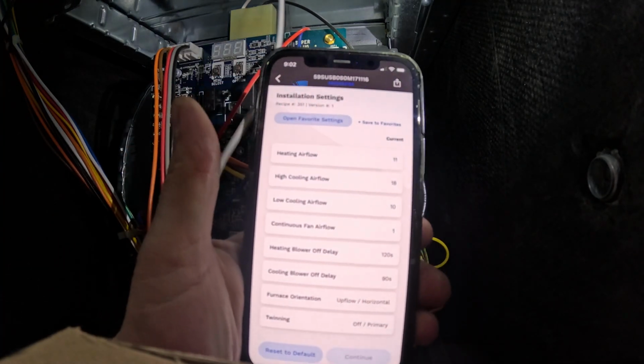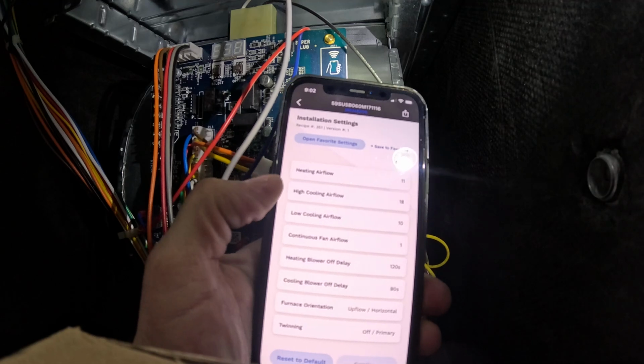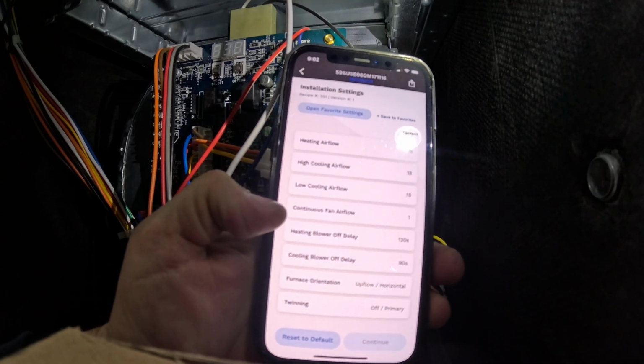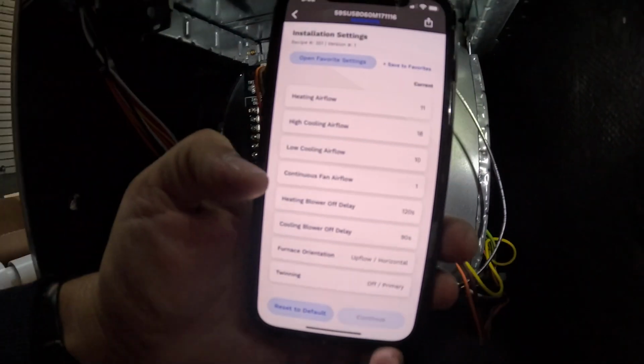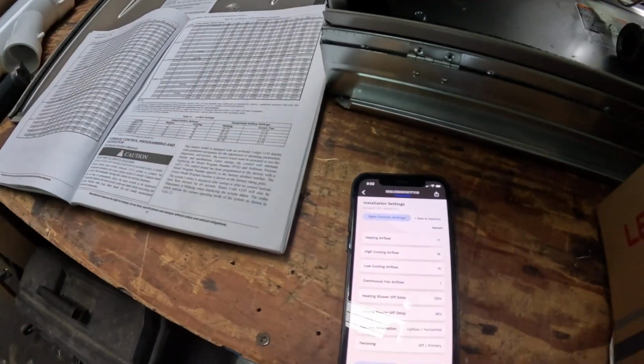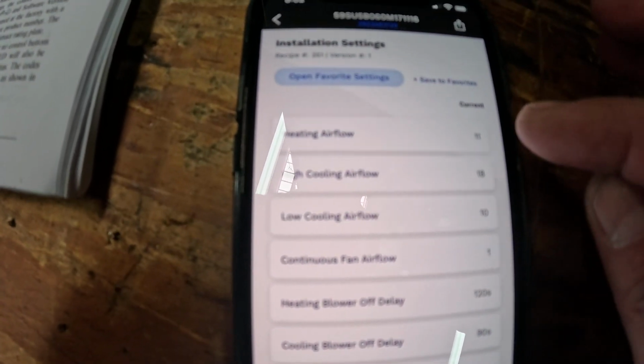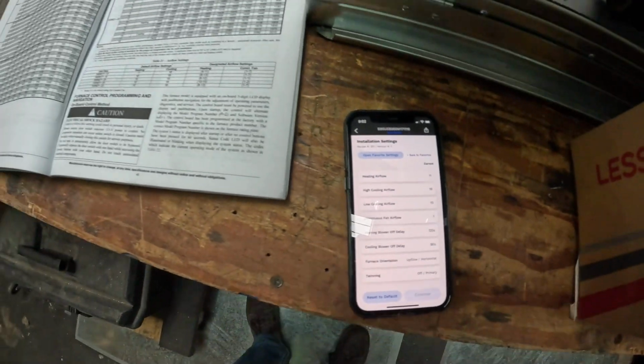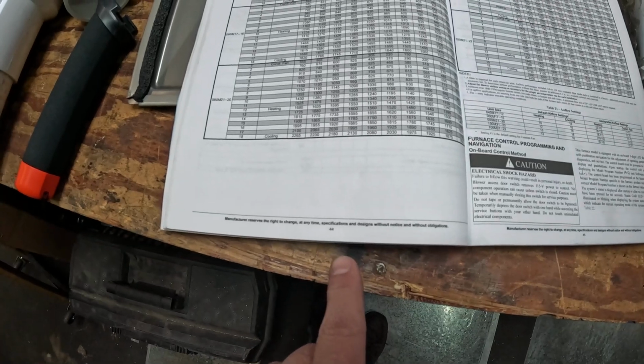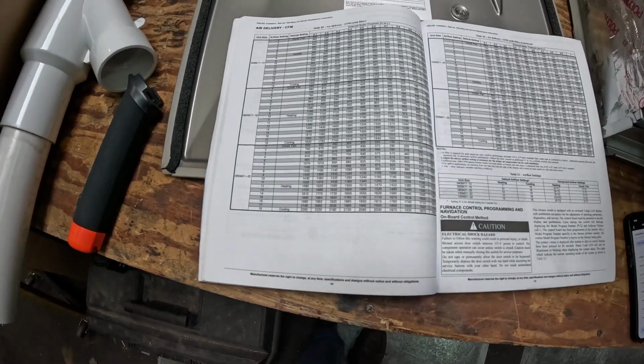So in the settings here, we have a whole bunch. We have the heating airflow, high cooling, low cooling, continuous fan. You can see that is set at 1. I'm going to grab my phone here and show you from the top angle. I'm going to go to heating airflow, and I can see it's set at an 11. Well, what does that mean? What you need to do is open your book. For this one, it's on page 44. A lot of books, it's on page 20. But we're going to find the 060 model right there. And you're going to look at what the constant fan is set at, a 1. The heating default is set at a 10. And then the cooling is at an 18.